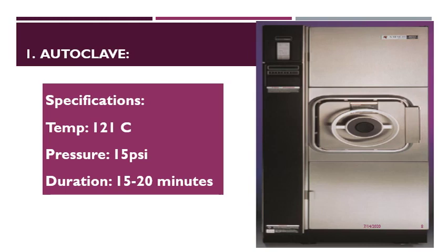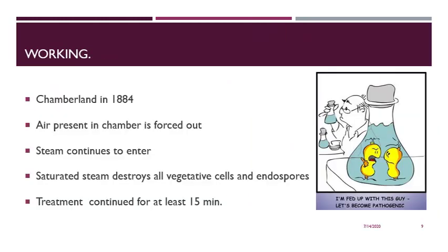Here are some specifications while using the autoclave: the temperature should be 121 degrees centigrade, pressure has to be 15 psi, and duration will be 15 to 20 minutes. Then if we study the working, Chamberland was the first scientist who studied the autoclave in 1884.